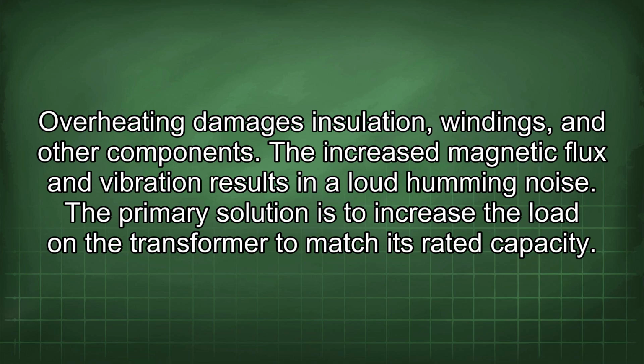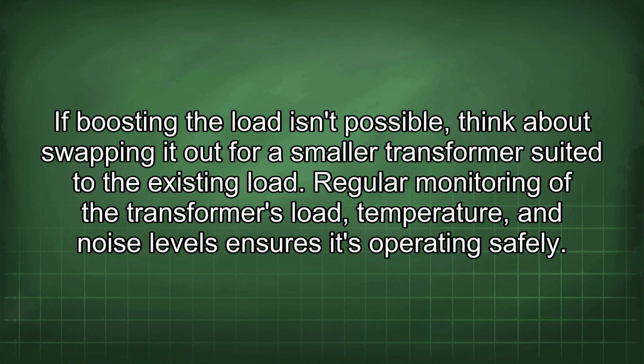The primary solution is to increase the load on the transformer to match its rated capacity. If boosting the load isn't possible, think about swapping it out for a smaller transformer suited to the existing load. Regular monitoring of the transformer's load, temperature, and noise levels ensures it's operating safely.